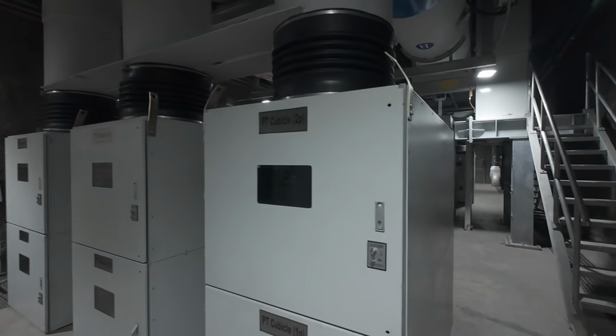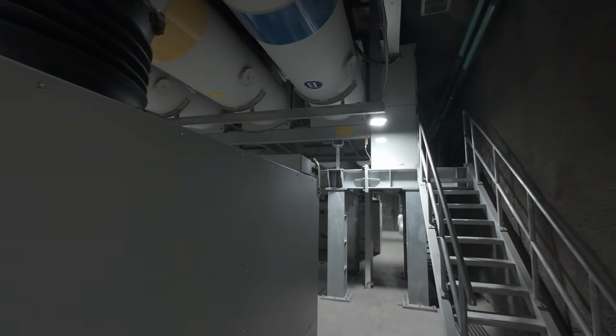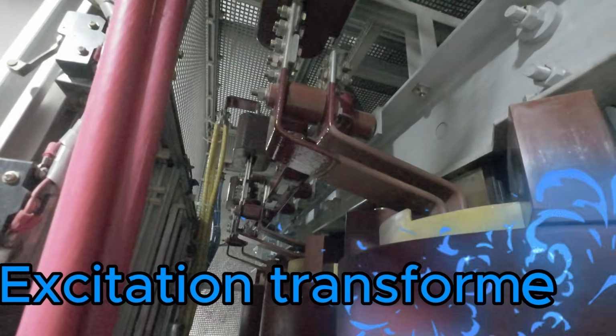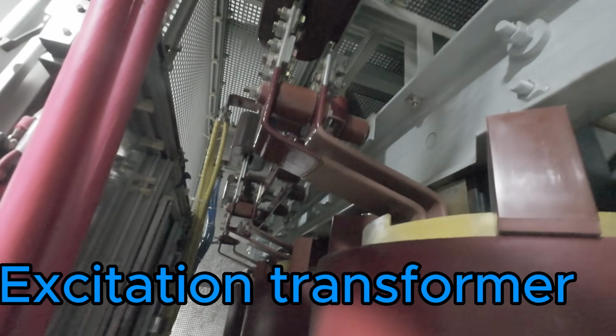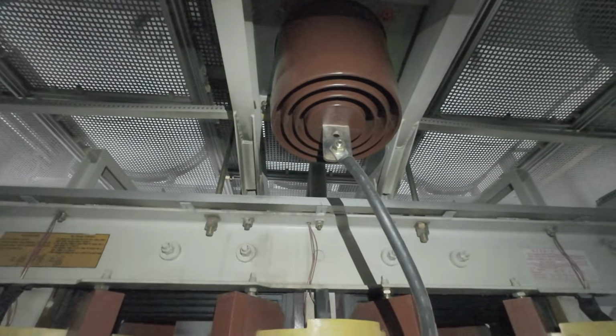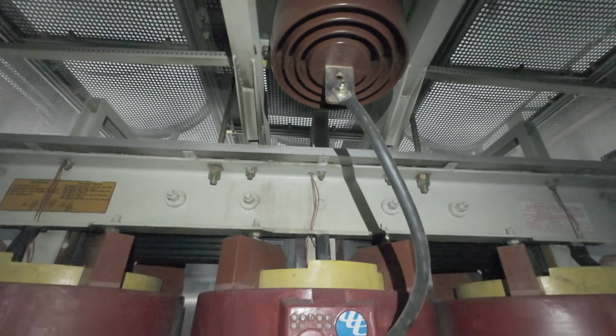The static excitation system has four major components. First comes the excitation transformer. A hydro generator may produce 15 to 20,000 volts AC, far too high for the excitation equipment. So the transformer steps that voltage down to around 600 to 900 volts AC.